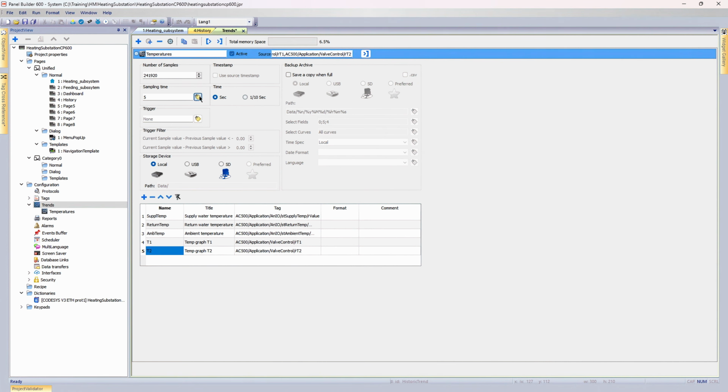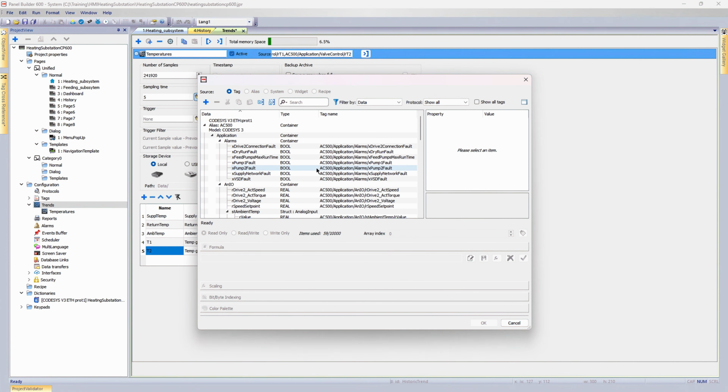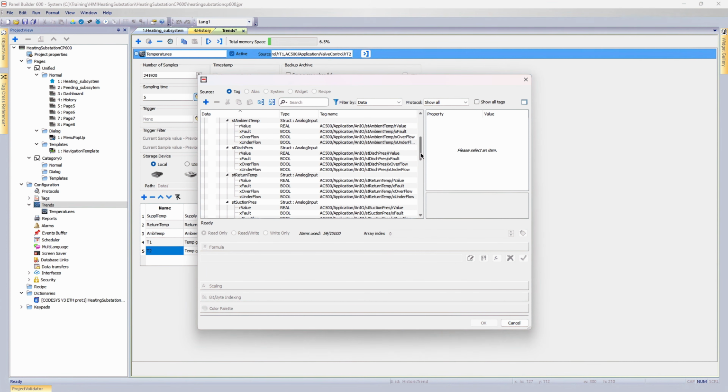It's also worth noting that the sampling time doesn't have to be a fixed number. You can attach it to any tag and then control granularity of data in the trend buffer during runtime. You can even stop logging for a specific buffer entirely by setting this sampling time to 0. It could be a way to conserve trend buffer memory when process or machine is sitting idle.